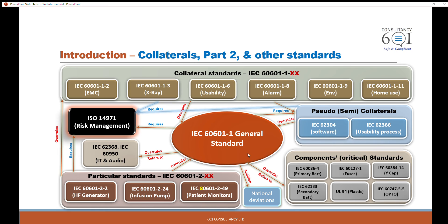When it comes to batteries, IEC 60601-1 requires that the battery shall meet the requirements of IEC 62133. You will also need to take note of the version cited inside the standard, and it also depends on the version of the general standard you are using.